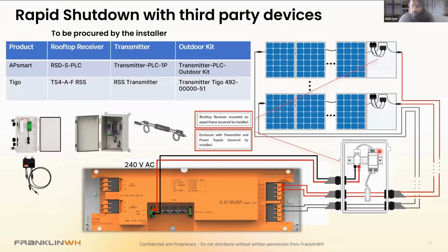With AP Smart, you typically have a transmitter and a transformer as well. All we provide is 240-volt AC output to the outdoor kit. That 240-volt AC gets terminated to the transformer, which then converts it to 12-volt DC, which is all the transmitter can support. So please do not connect the power supply from the aPower S directly to the transmitter — that is certainly not good.